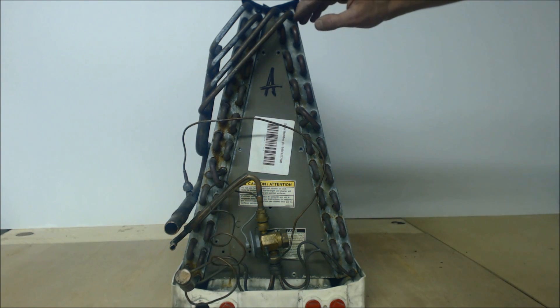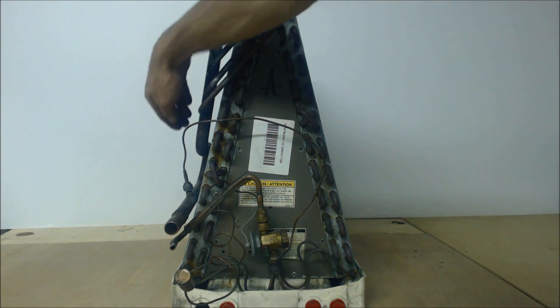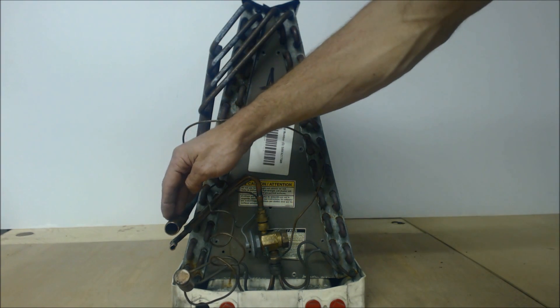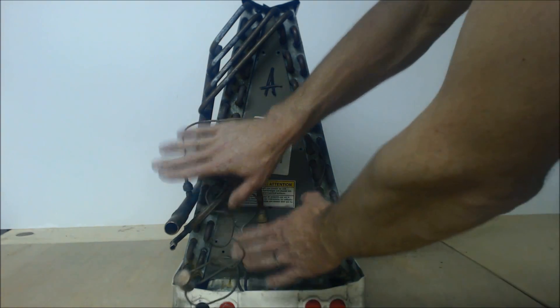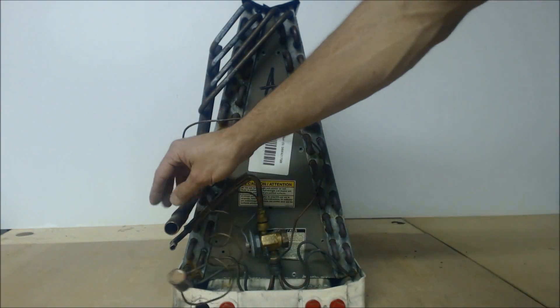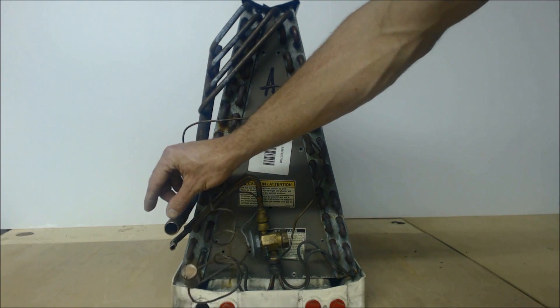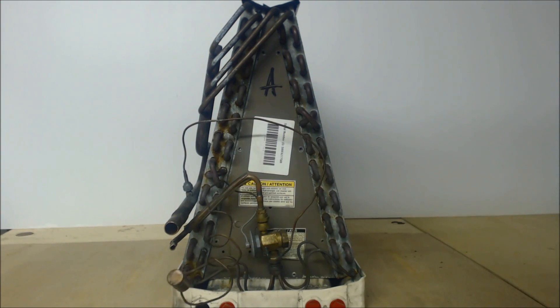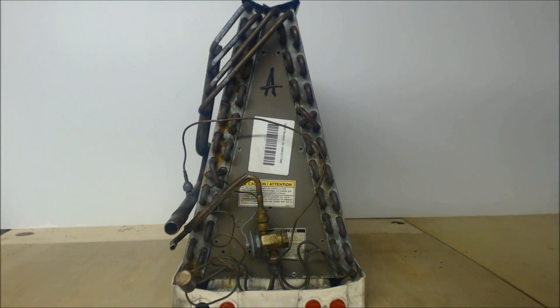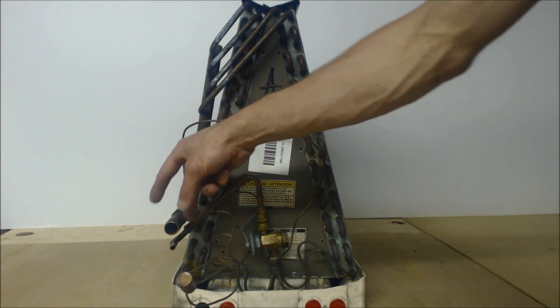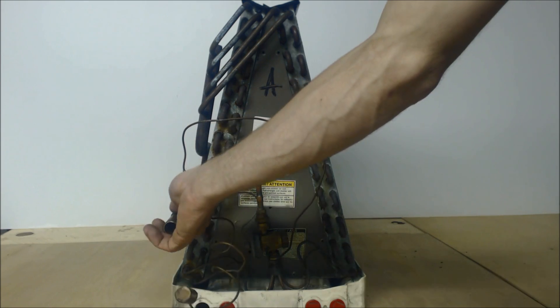From there on it gets superheated, and the temperature increase in vapor form is where it comes out. This is the superheat. This would be out of the evaporator coil box. If you had an access port here and a temperature probe, that would be reading your superheat.